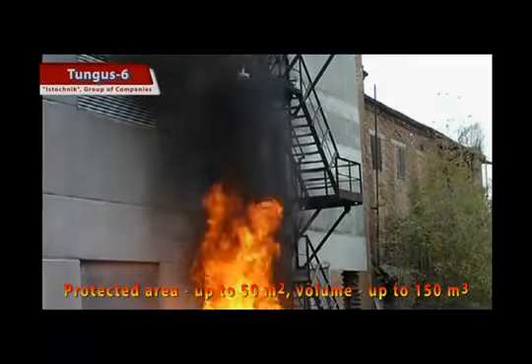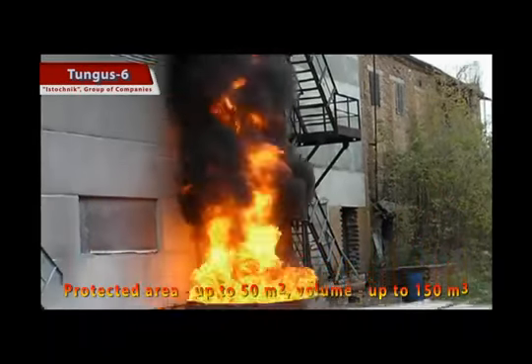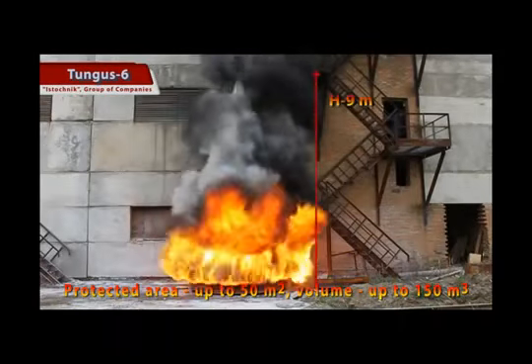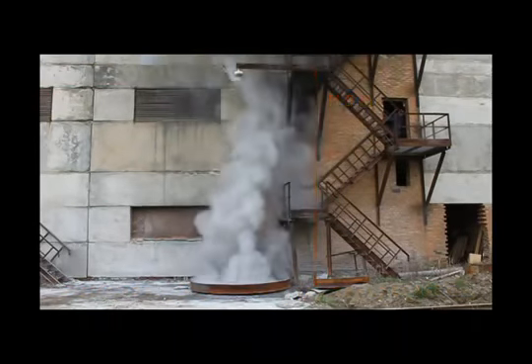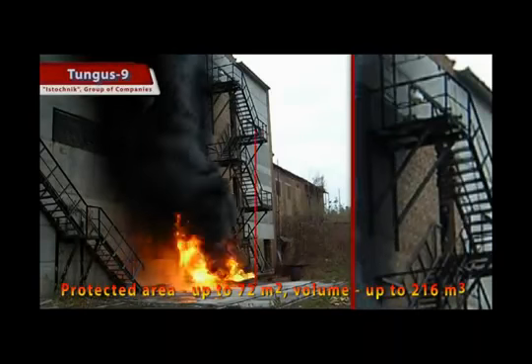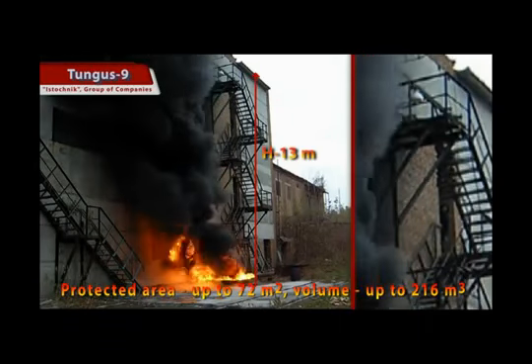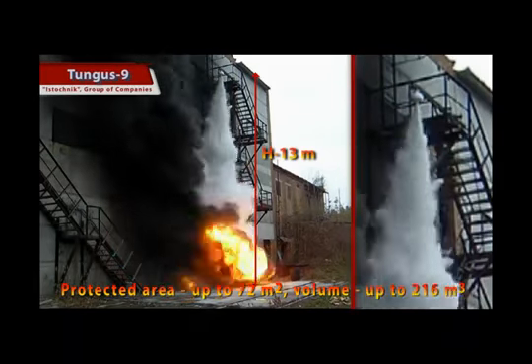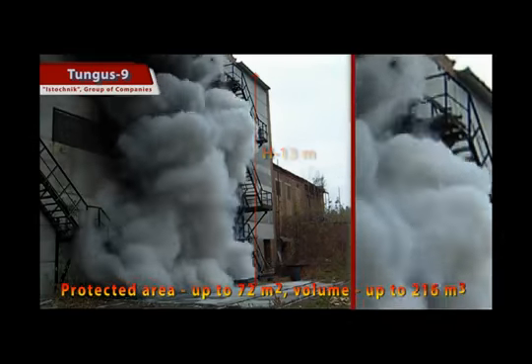High efficiency of the modules is provided owing to the high firefighting ability of the powder and high intensity of powder supplying to the seat of fire. The modules are actuated from an electrical signal of low power. Starting current is 120 mA. So the devices have rather simple design and reasonable price, available for mass consumption.